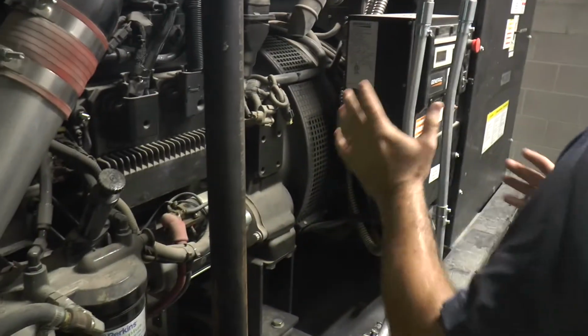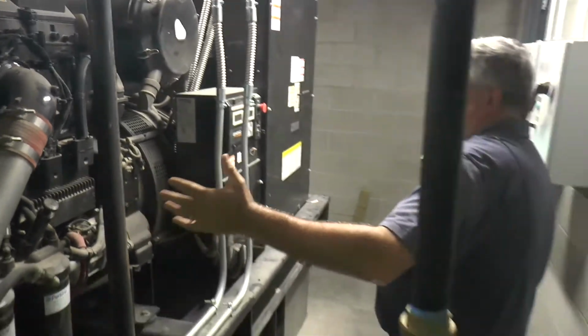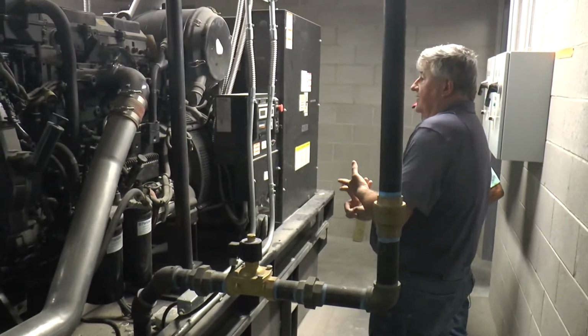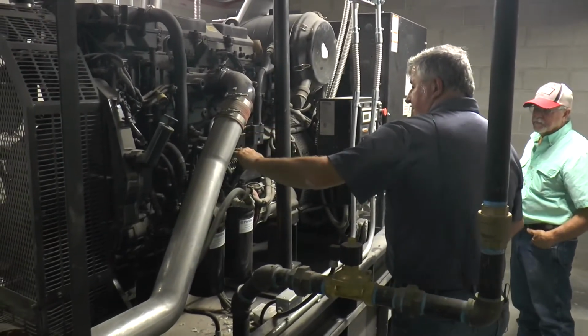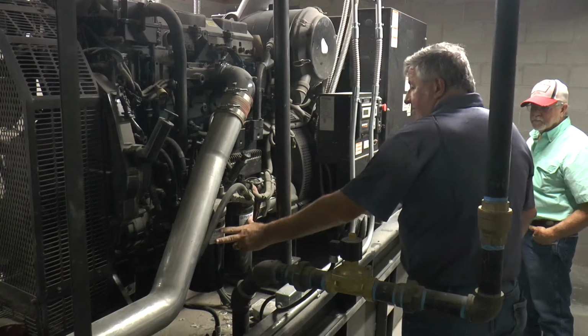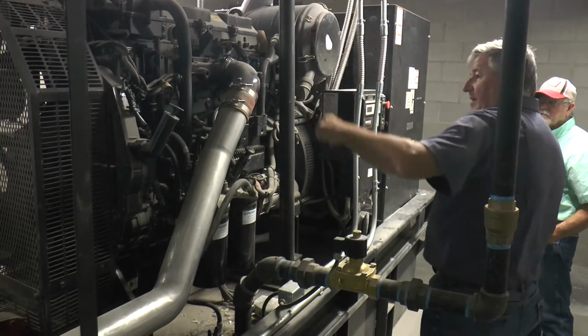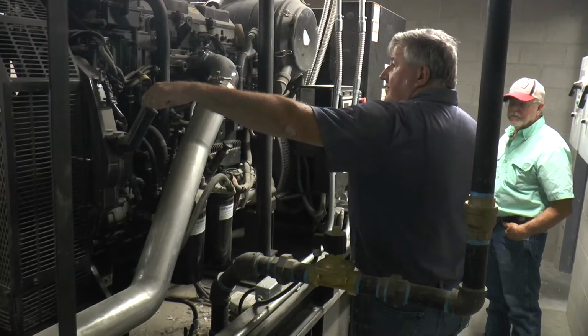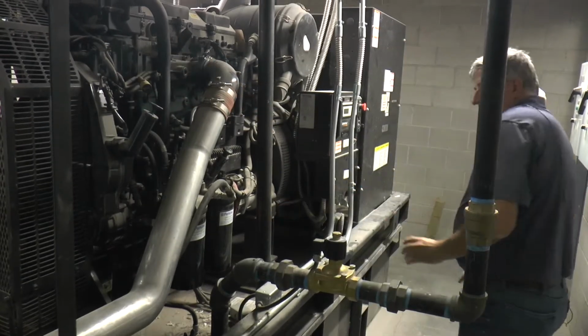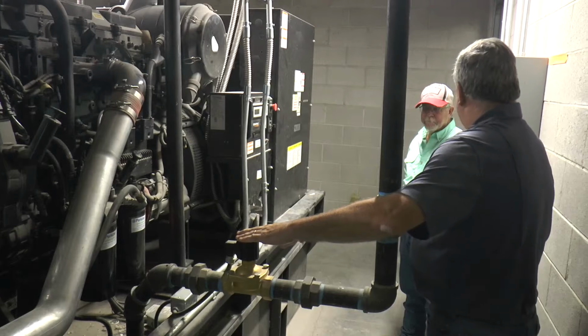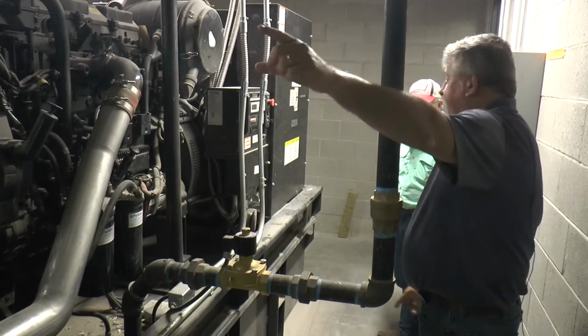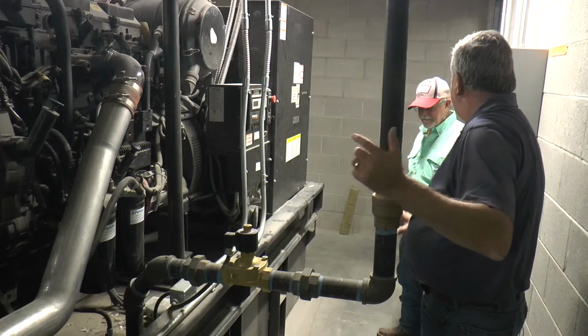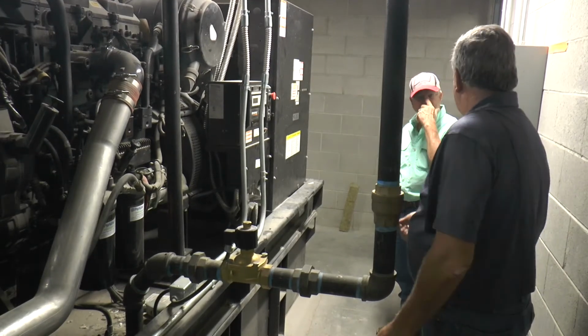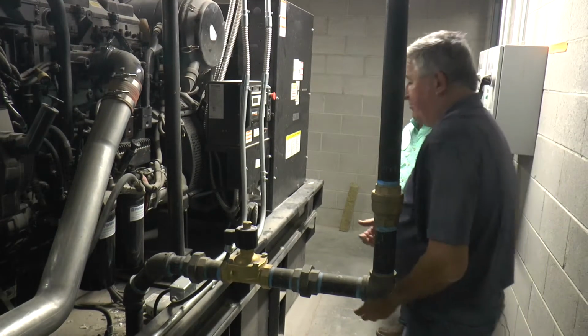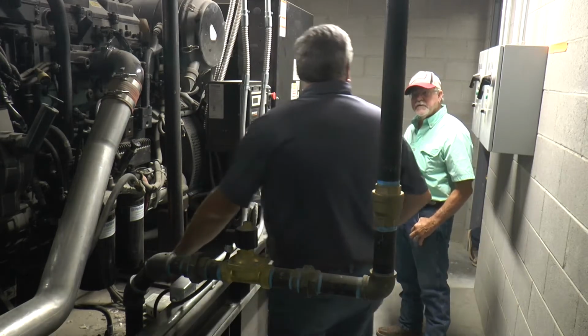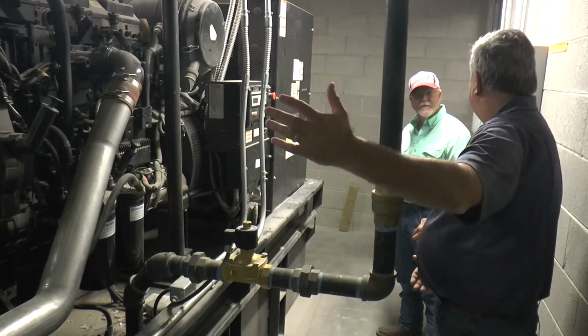Engine starter. As you're looking at the engine, you just want to look at it cursorily. Look for any oil leaks, any coolant leaks. Engine ECM, priming pump, fuel filters. Oil filters are going to be on the other side. Fill, breather tube. Engine also is equipped with a remote fill station. So this fuel tank is filled from an outside box. City of Phoenix does not allow you to bring a fuel line in the building anymore. Where some generators you just brought it in and you plumbed it right to the tank. They don't allow you. They want you to fill it from the exterior of the building.